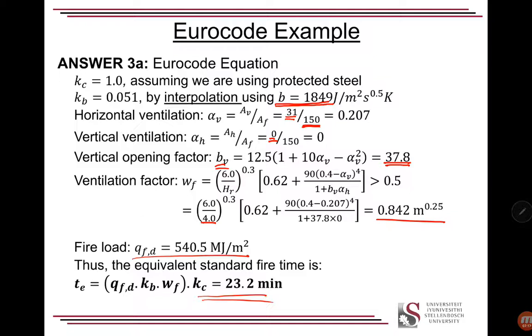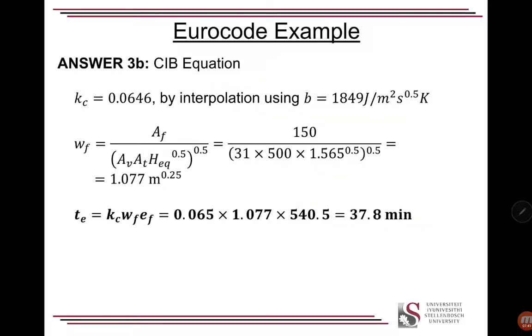Now, you'll see in our, just looking at the graph early, you can see that's probably on the low side. We were expecting 30, maybe 40 minutes, but yeah, this is on the low side. But it's based upon a whole bunch of equations above, very empirical. So you could see you would have a different result depending on how you calculated, whether you were using temperatures or materials or area under graph, various different ways you get different answers.